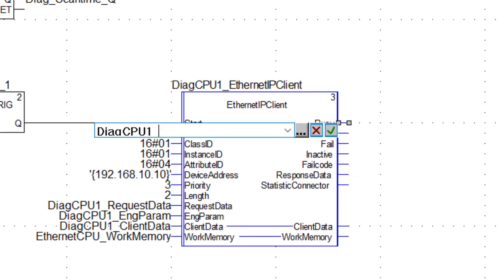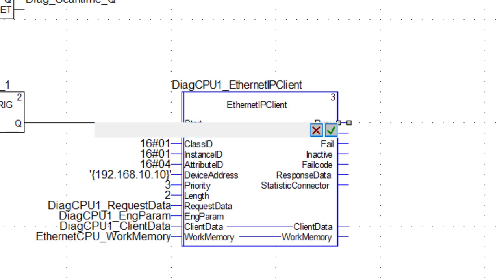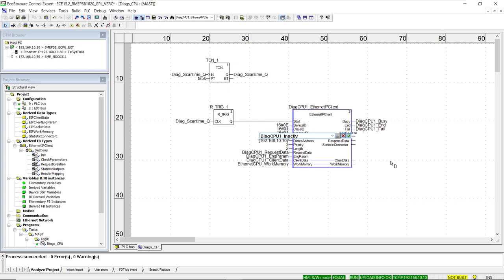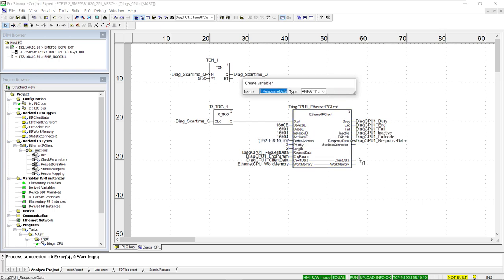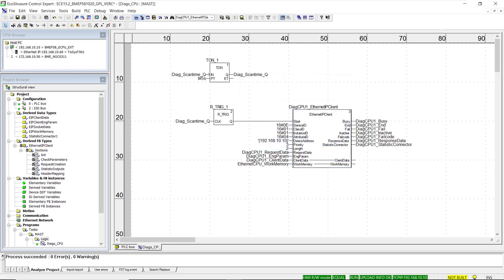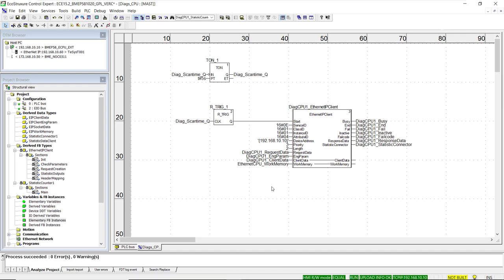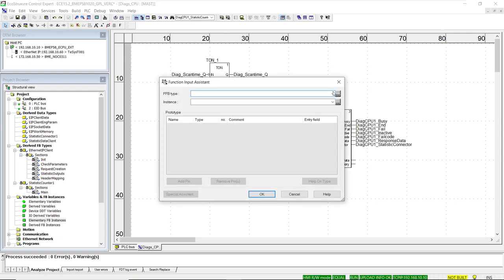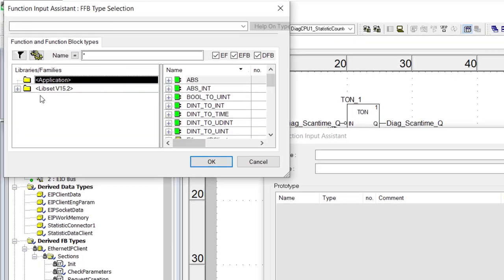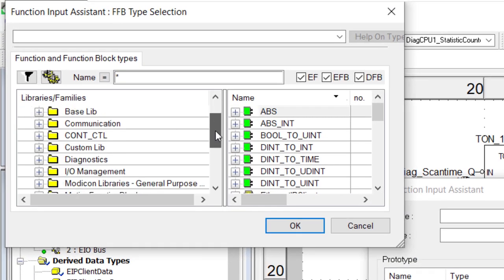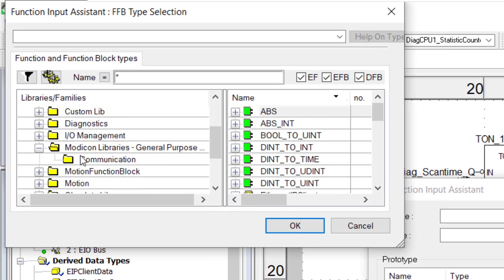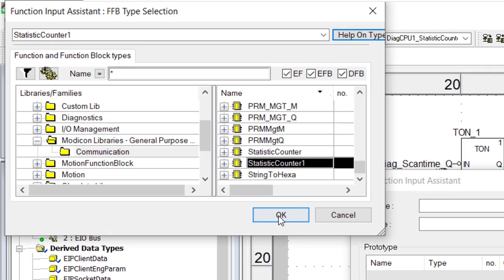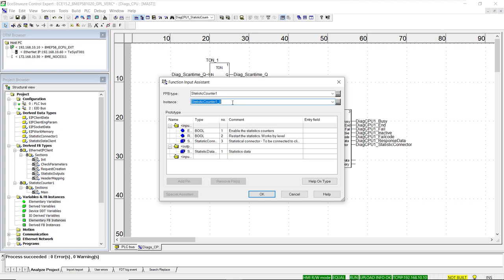The next function block is optional but extremely useful for diagnosing correct operation of the client function block. We find it in the general purpose library folder, the communications folder — it is the statistic counter number one function block. We follow the same naming convention, adding the prefix diagcpu1 to the function block instance name, then creating variables for the input and output pins using the prefix underscore pin name syntax.